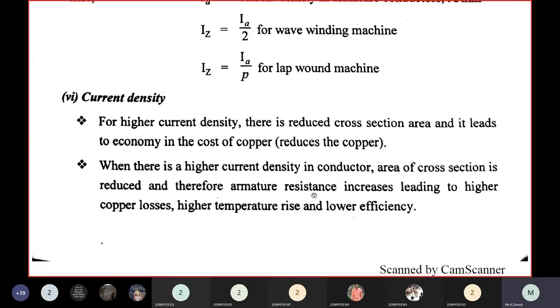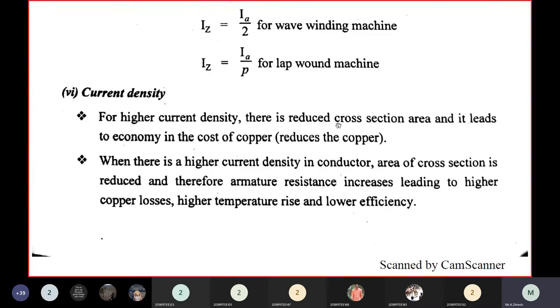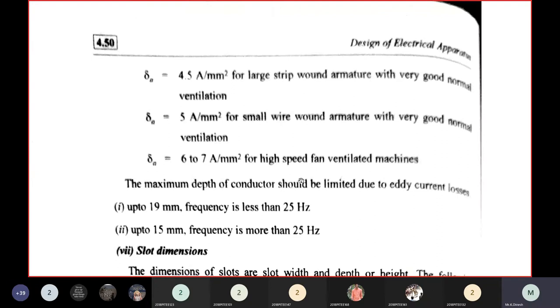The purpose of current density: it reduces conductor cross-section area, leading to economy in copper cost. However, high current density causes higher copper losses, higher temperature rise, and lower efficiency. Current density values: 4.5 A/mm² for large strip-wound armatures with normal ventilation; 5 A/mm² for small wire-wound armatures with good ventilation; 6 to 7 A/mm² for high-speed fan-ventilated machines.